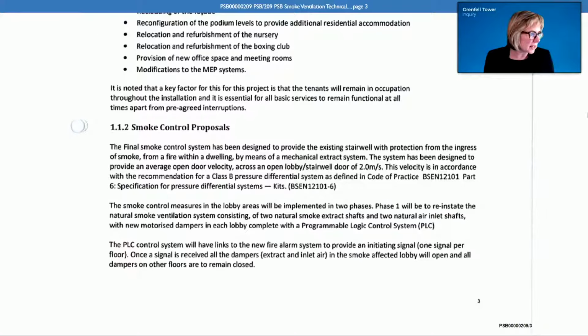And it goes on to say the smoke control measures will be implemented in 2 phases. Phase 1 is to reinstate the natural system, and then it goes on at the bottom, the PLC control system will have links to the new fire alarm system to provide an initiating signal. Once the signal is received, all the dampers in the smoke-affected lobby will open and all dampers on other floors are to remain closed.